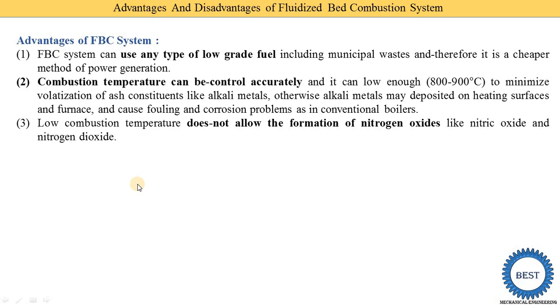The third advantage is that the low combustion temperature does not allow the formation of nitrogen oxides like nitric oxide (NO) and nitrogen dioxide (NO₂). When combustion temperature is above 1100°C, NOx production is higher and pollution increases. But in the FBC boiler the temperature is lower, so nitrogen oxide pollution is reduced.